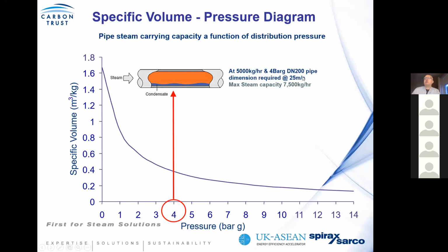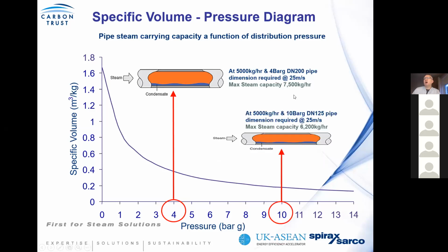The reason why you need this size pipe is that you need to ensure that you can accommodate the 5,000 kgs an hour within a standard pipe size. If you go to the smaller DN of 150, you won't be able to accommodate the 5,000 kgs an hour. In this scenario, you might get a total of 7,500 kgs an hour. But the key point is that you need a DN 200. Now, if we look at 10 bar, for example, to get the same 5,000 kgs an hour, you actually need a DN 125 size pipe. Although the total capacity will reduce to 6,200 kgs an hour, we're looking at a process that only needs 5,000.